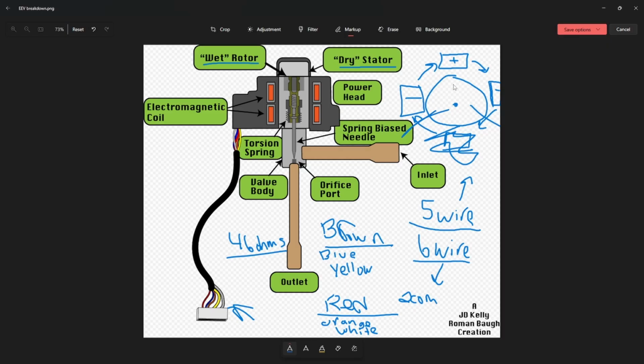So once you lose a pole, that stepper motor is dead in the water. It can move in this little section, that's it. But once it hits this area, it's not going to open or close. It's not going to do anything. So once you lose a coil, that's it. Stepper motor's done. So most EEVs expect a 40 to 50 ohm reading. Doesn't matter brand. It should be 40 to 50 ohms for most stepper motors out there. Doesn't matter if it's Trane, Carrier, or Daikin. They want to see 40 to 50. That's a normally operating stepper motor.